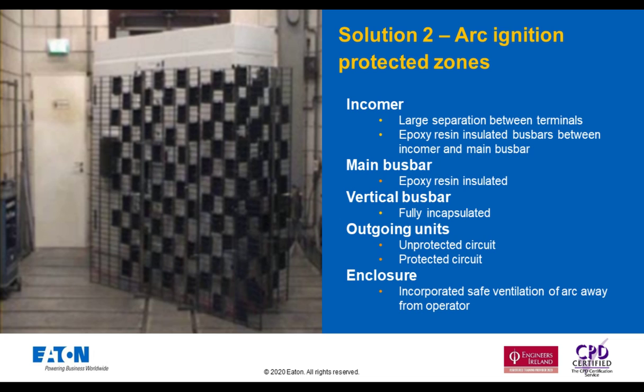So the arc ignition protected zones means it remains a remote possibility that an arc can physically be generated, due to the constructional barriers and insulation as part of the design. And so within the standard, we have 7 testing criteria. The first testing criteria is personal protection, and this is achieved when criteria 1 to 5 are fully fulfilled. So the 5 criteria are that during the test, correctly secured doors and covers do not open. So during the test, they're usually closed and shut. In the event of an arc happening, they don't open.